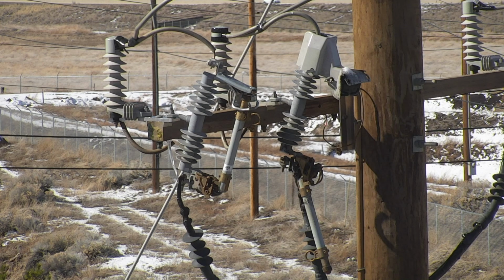So this is that power pole. You can see C phase, this guy over here, here's B phase. A phase stayed in place, but because the arc flash started over here and flew this away, it blew this guy out. But the energy had dissipated enough that it didn't blow this guy out.